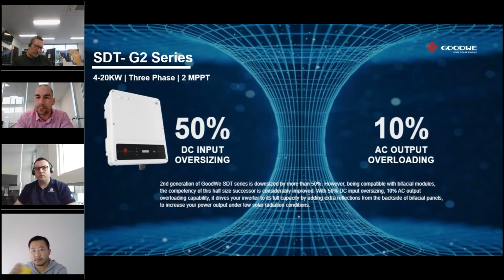The SDT G2, which I mentioned just before, has 50% oversizing. So that now means that our entire 3-phase range has the capability to oversize by 50%. As you know, you can claim STCs on up to 33%. However, from an inverter manufacturer standpoint, we're comfortable with you oversizing by 50%. And AC overloading, which we mentioned before: the SDT G2 series from 5 to 20 kilowatts has 10% AC overloading. So if you've got a 10 kilowatt inverter and you pair that with 11 kilowatts or more of panels, it's actually going to output 11 kilowatts.